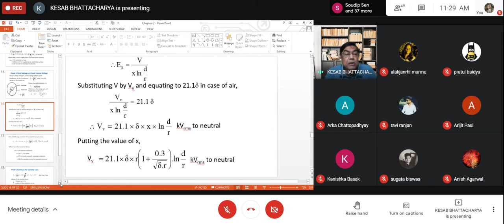But again, this is not all. As in the case of disruptive critical voltage, we introduced some factor, here also we have to introduce some factor, again to take into account the surface conditions, and in this case it is denoted by m suffix v.